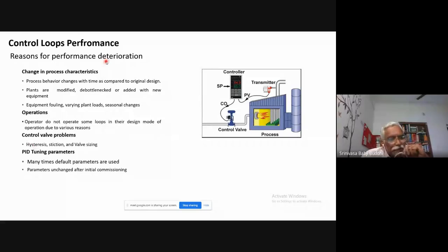Then the last one is the tuning parameters. Typically, when you commission the plant in the initial stages, you do the tuning of all the control loops and make sure that the plant is working properly. But over a period of time, because of all these changes in the process behavior, you need to do retuning of the PID controllers. If you do not do that, the tuning parameters being not appropriate will again lead to poor performance of PID controllers. So these are all the factors that contribute to the deterioration in the plant performance and the PID controller performance.